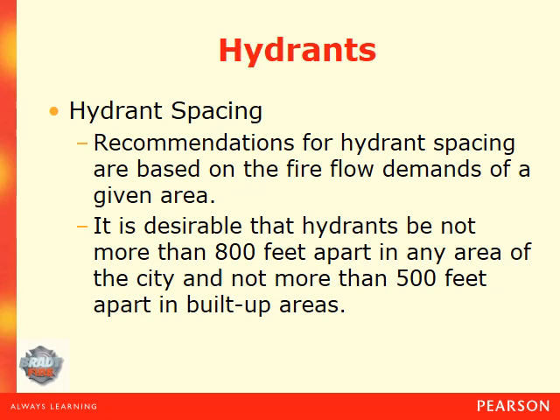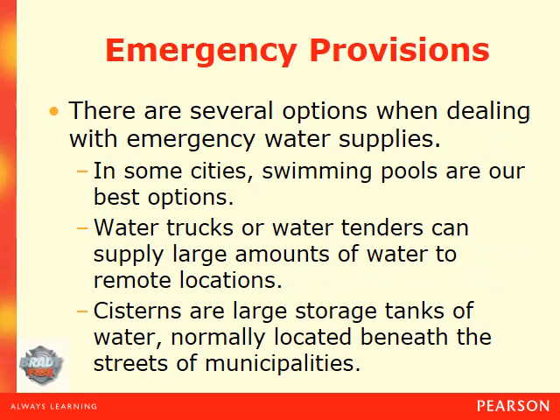Recommendations for hydrant spacing are based on the fire flow demands of a given area. It is desirable that hydrants be no more than 800 feet apart in any area of the city and no more than 500 feet apart in built-up areas. For emergency water supplies, in some cities swimming pools are the best option. Water trucks or water tenders can also supply large amounts of water to remote locations, and cisterns are large storage tanks of water normally located beneath the street of a municipality, often containing runoff water.